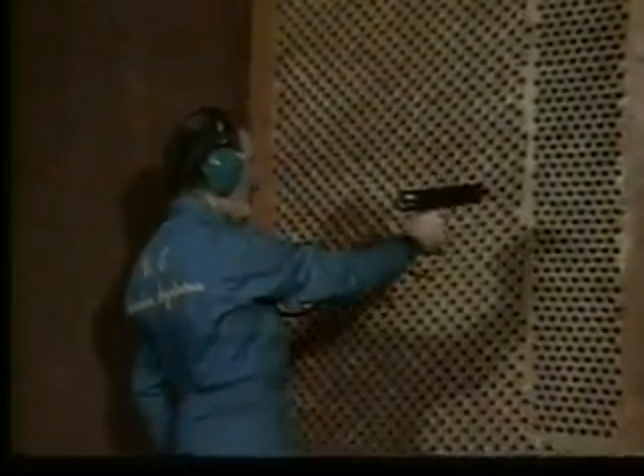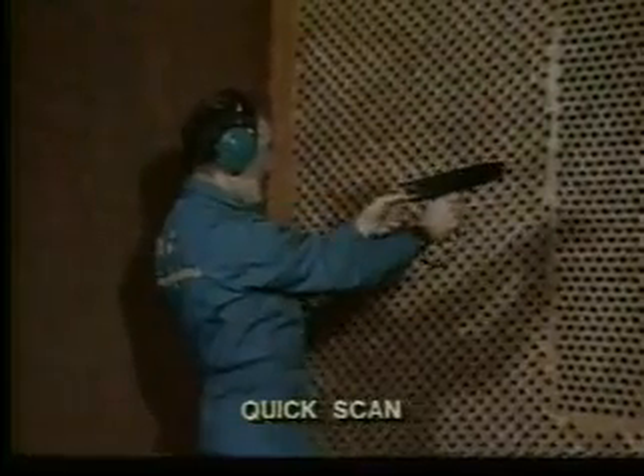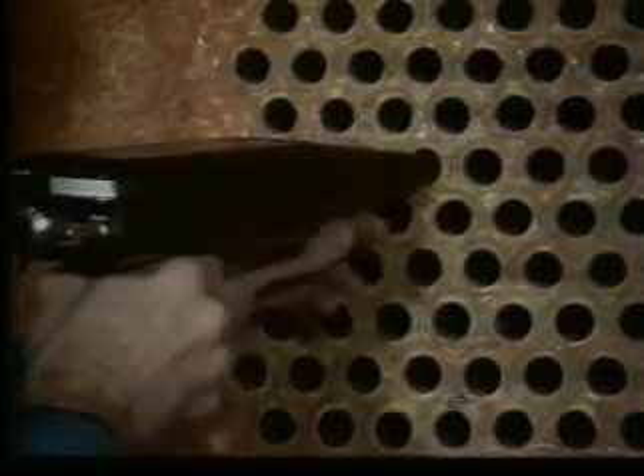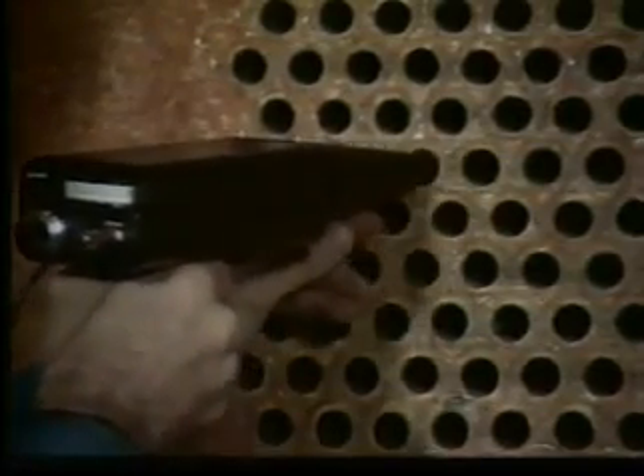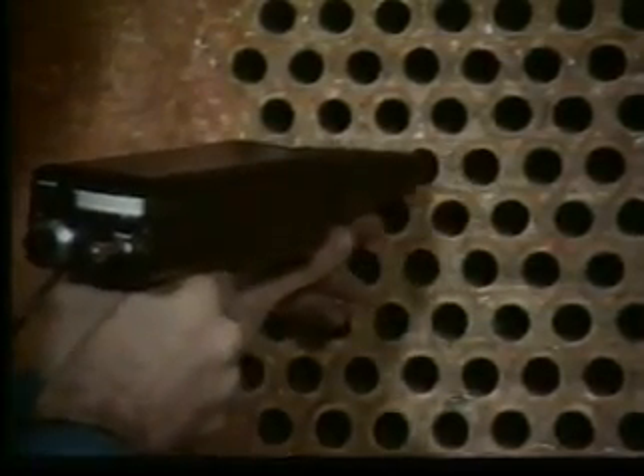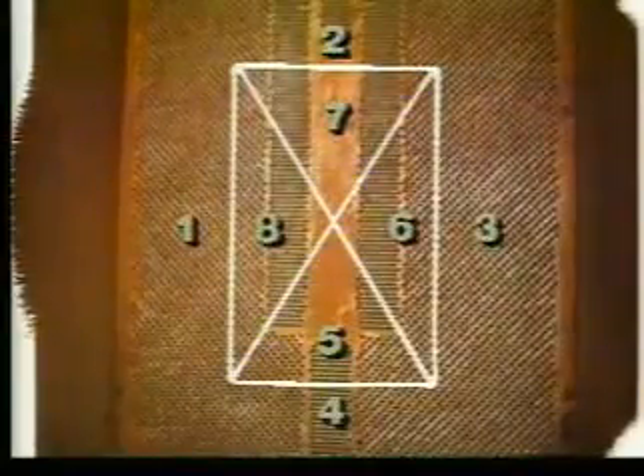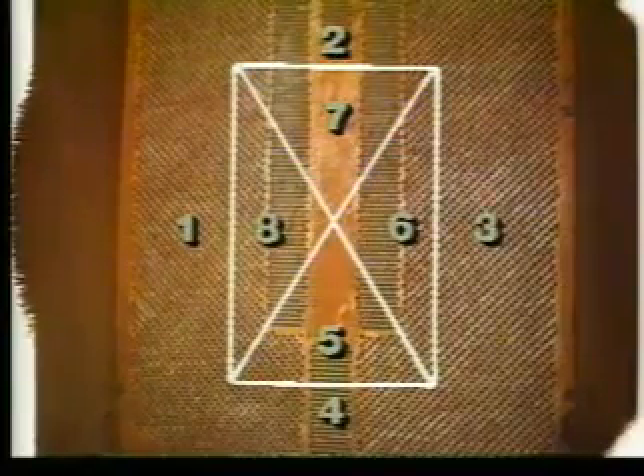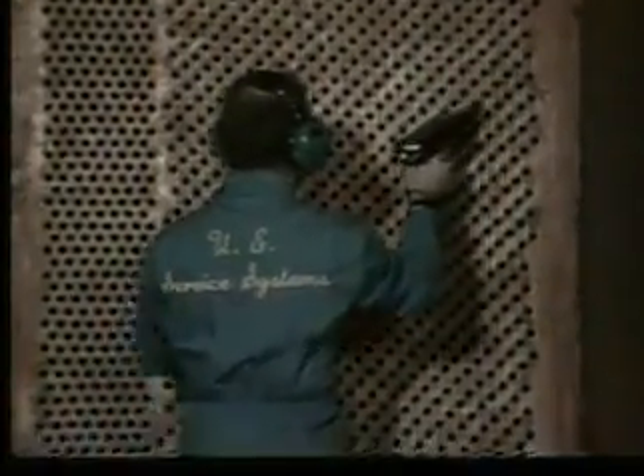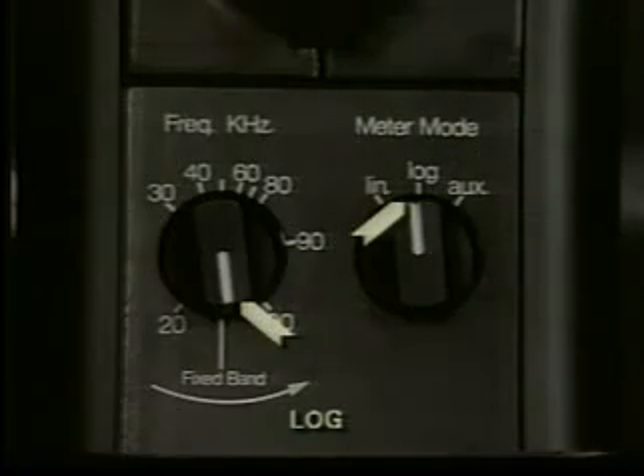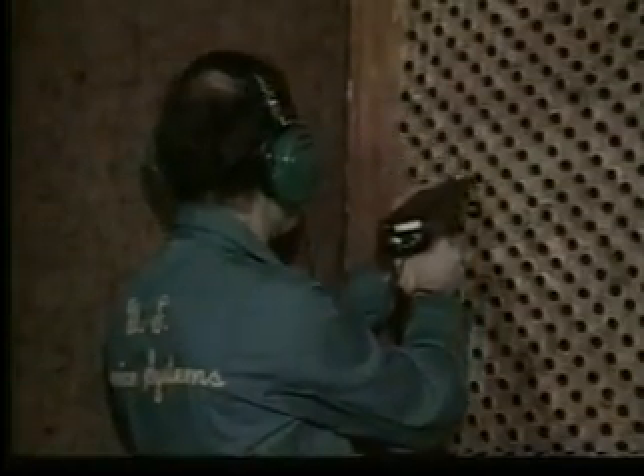To locate a leak site with the ultraprobe, conduct a quick scan, listening for an obvious problem area. If a sound pops out from the background noise, you may be able to get closer and pinpoint the leak site this easily. If a quick scan is inconclusive, divide the condenser tubes into testing zones. Start scanning peripheral tube zones where sounds are loudest. Set the ultraprobe to log and use it in the fixed band position. With the rubber probe, scan a sample tube and adjust the sensitivity to read 50 on the meter. Scan for the loudest deflection in the test zone.